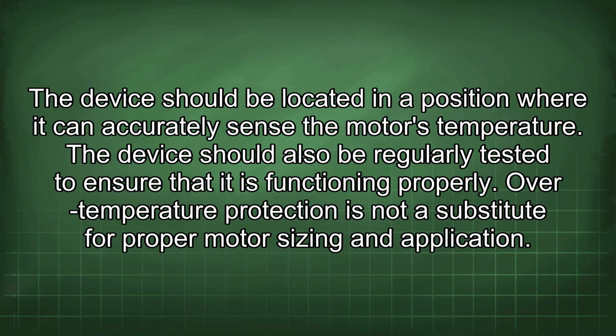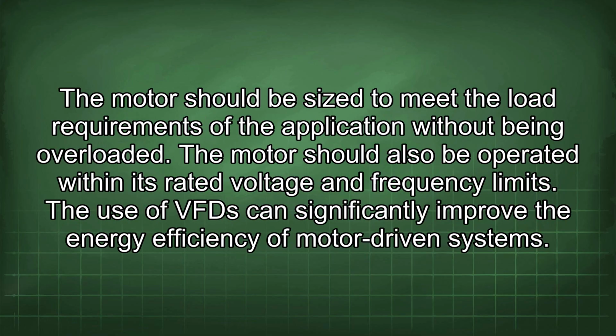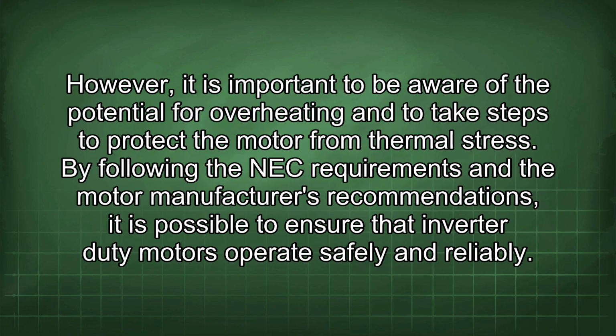Over-temperature protection is not a substitute for proper motor sizing and application. The motor should be sized to meet the load requirements of the application without being overloaded. The motor should also be operated within its rated voltage and frequency limits. The use of VFDs can significantly improve the energy efficiency of motor-driven systems. However, it is important to be aware of the potential for overheating and to take steps to protect the motor from thermal stress. By following the NEC requirements and the motor manufacturer's recommendations, it is possible to ensure that inverter duty motors operate safely and reliably.